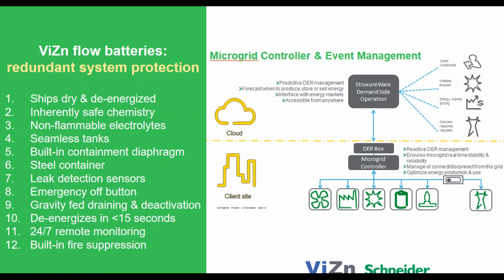When you hit this emergency off button, it automatically drains the system in 15 seconds. These systems are connected to the building's infrastructure using bus bars, big thick wires. Within 10 to 15 seconds of being de-energized, a fireman could hang a crowbar on that bus bar and there would be no voltage and no current. So if any current or voltage should ever overheat a fuse or blow a fuse, or short out a wire inside the container as a last resort, if that ever creates any smoke, there's built-in fire suppression that's both automatic and can be tied into the building's safety systems as well.